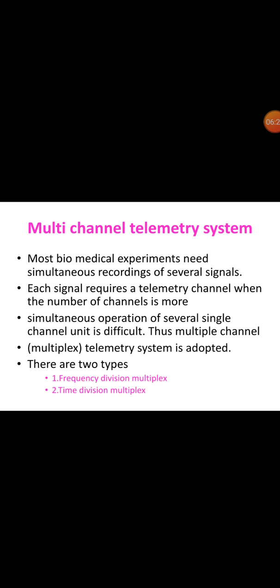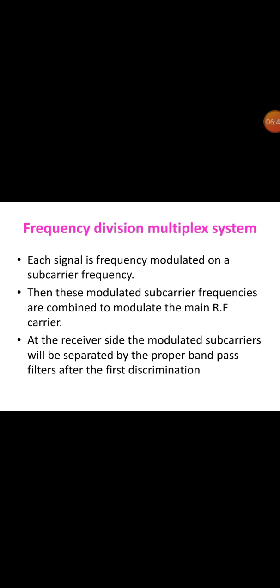The second category is the multichannel telemetry system. Most biomedical experiments need simultaneous recording of several signals. Each signal requires a separate telemetry channel, and when the number of channels is more, simultaneous operation of several single channel units is difficult. Thus, a multiple channel telemetry system is adopted. It can be divided into two types: frequency division multiplexing (FDM) and time division multiplexing (TDM).